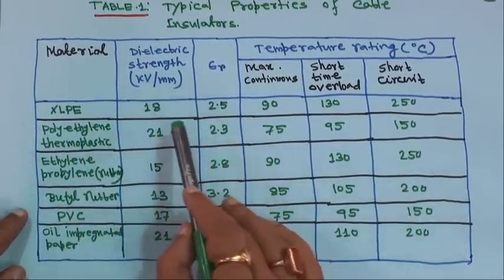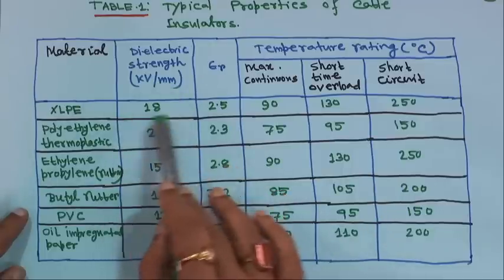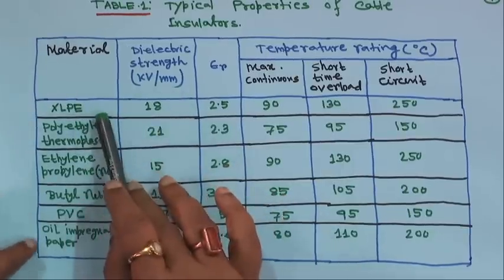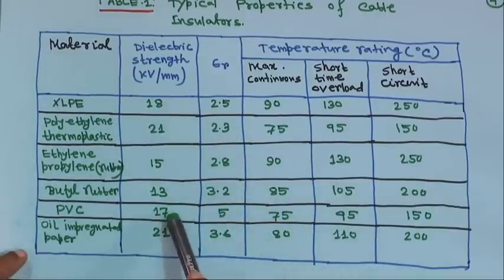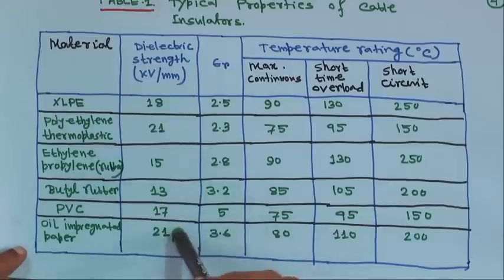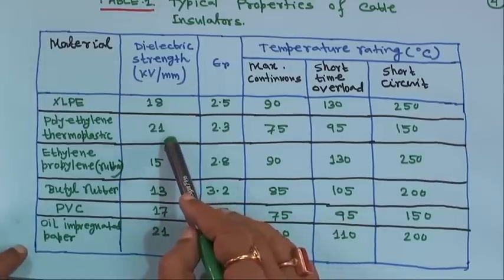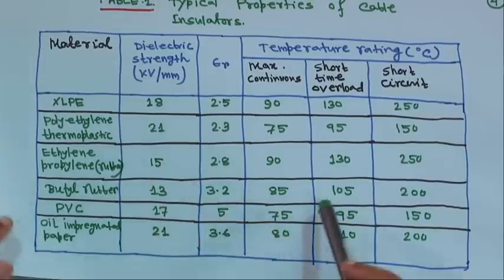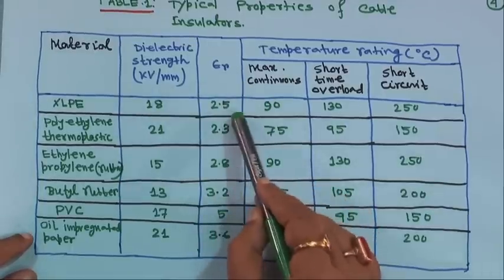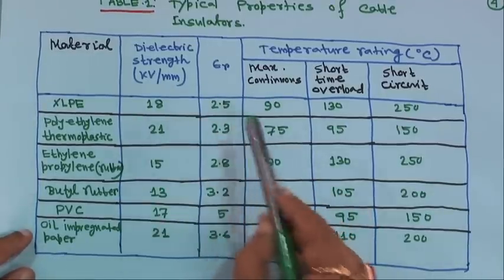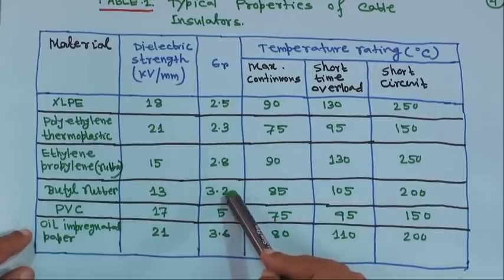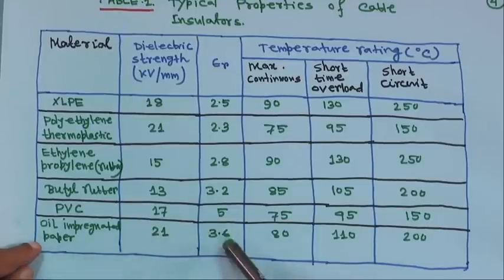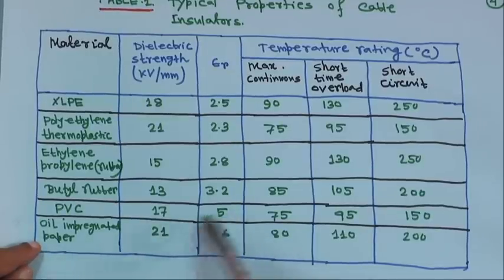Dielectric strength in kV/mm: XLPE is 18, polyethylene thermoplastic is 21 (maximum), ethylene propylene is 15, butyl rubber is 13, PVC is 17, and oil-impregnated paper is 21. Permittivity: XLPE is 2.5, polyethylene 2.3, ethylene propylene 2.8, butyl rubber 3.2, PVC is the highest at 5, and oil-impregnated paper is 3.6.